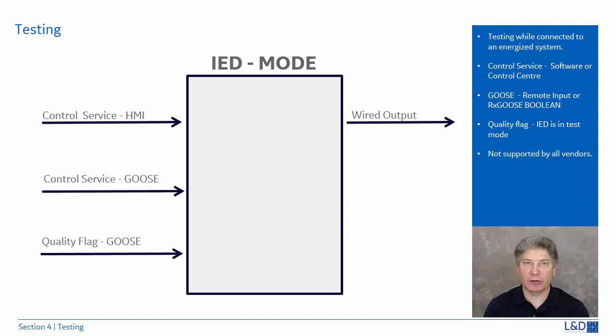Test mode allows the operator to control the functional testing of the elements while controlling the conditions of the outputs. We can control the mode of the IED by a control service such as an HMI through either software or a digital signal from a DMS. We can also control the mode via GOOSE as a control service via remote input or an R-GOOSE Boolean, or use the test quality flag. Based on the configurations for test parameters, we'll determine whether the output relays will operate.